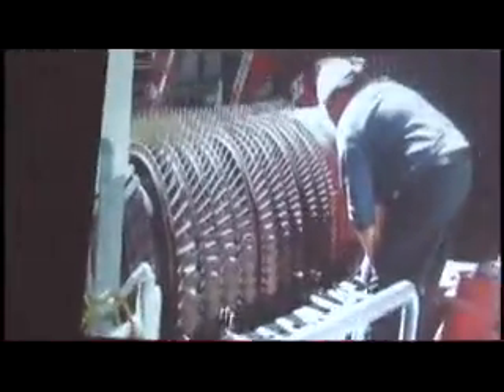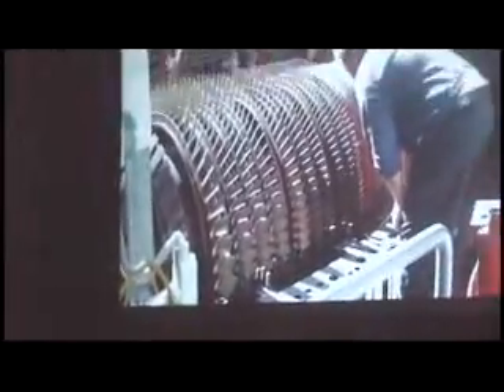There's a technician from Siemens during an outage, when we have them all torn apart, inspecting to see what kind of damage, or lack of it, he finds. We have to do that twice a year here, because having a hot flame in there is going to cause a certain amount of damage over time — microscopic cracks that need to be taken care of before they become more than microscopic.